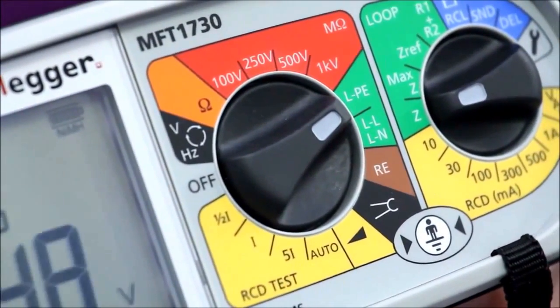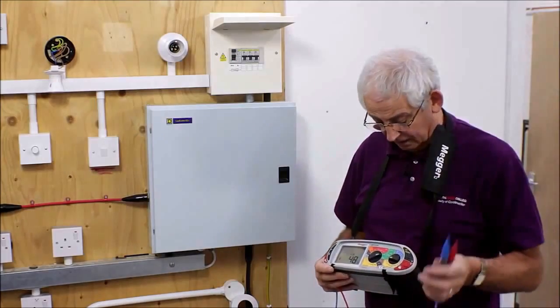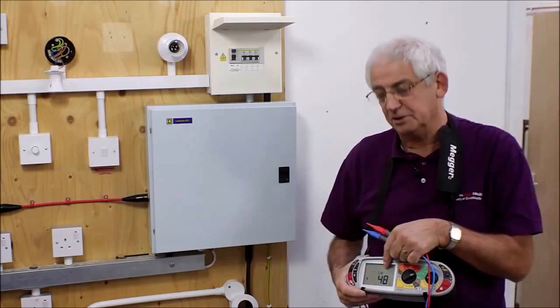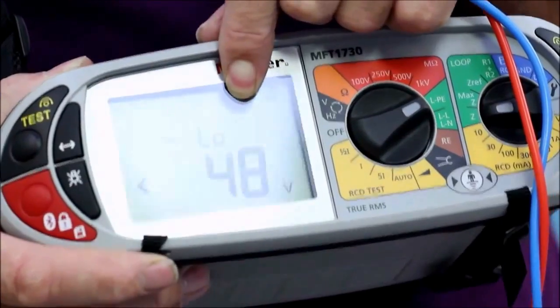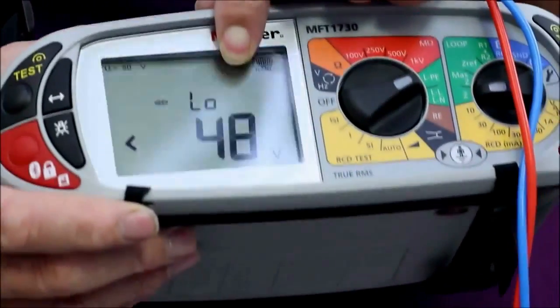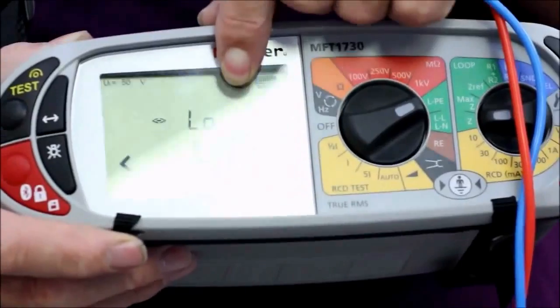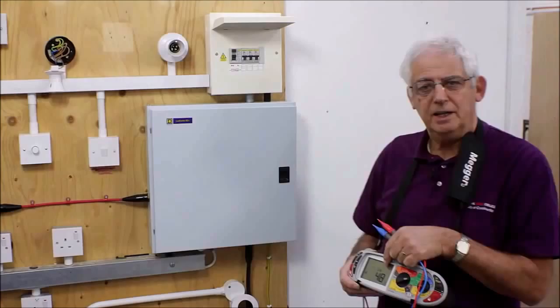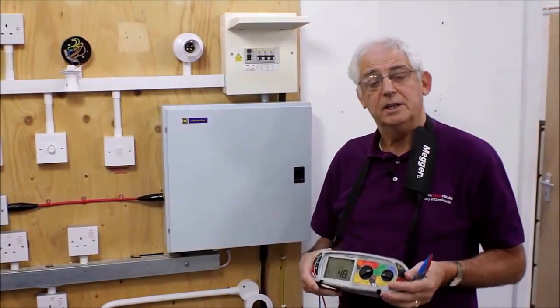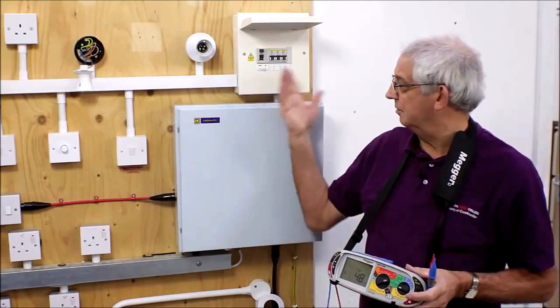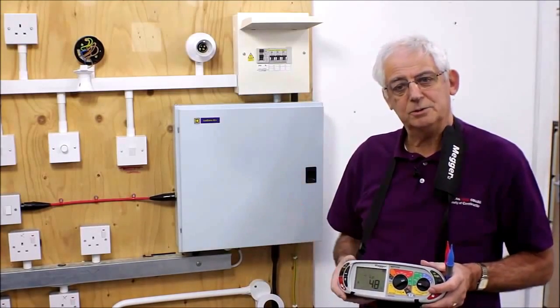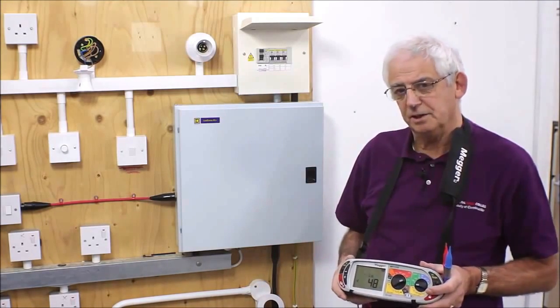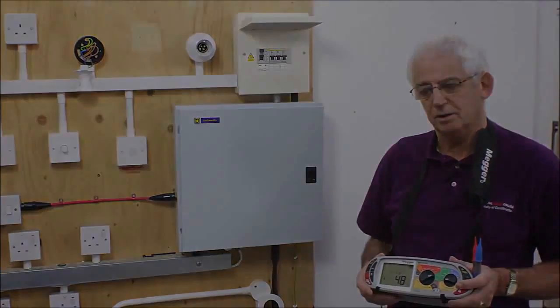Need to set my instrument to LPE and Z because that's what I'm doing. And because I'm using 2 leads, you can see the instrument tells me that it's a low current test. This won't trip the RCD. That's the whole object of the exercise. If I did it on a high current test, it will allow too much current to flow through the RCD and it will trip it. So low current test is very important where RCDs are involved.